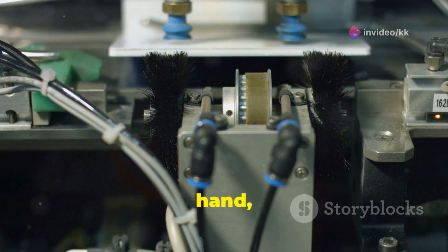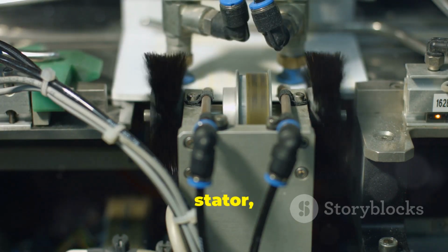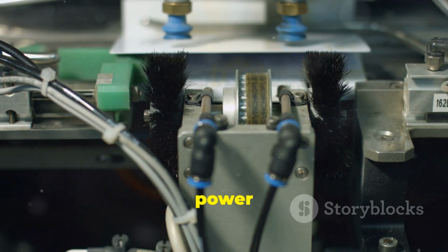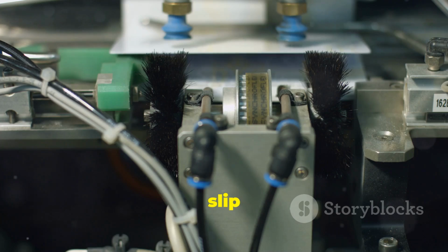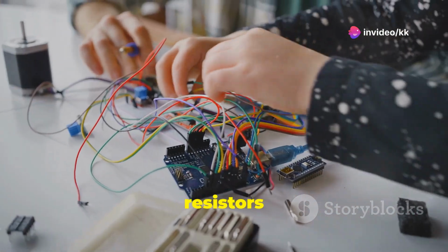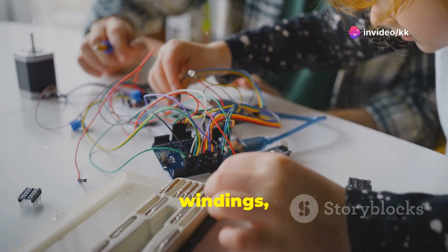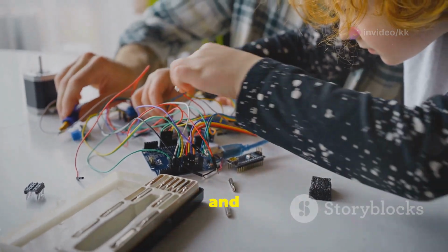Wound rotors, on the other hand, have windings similar to the stator, but instead of being connected to an external power source, they are connected to slip rings mounted on the rotor shaft. These slip rings allow external resistors to be connected to the rotor windings, enabling control over the motor's speed and torque characteristics.